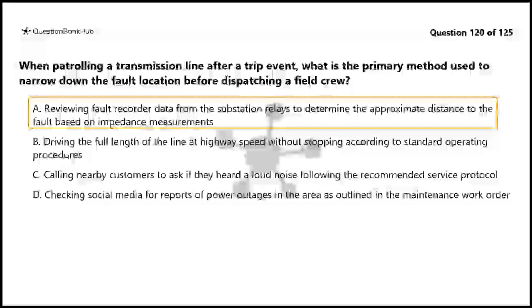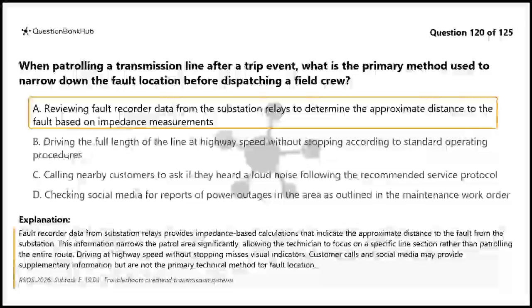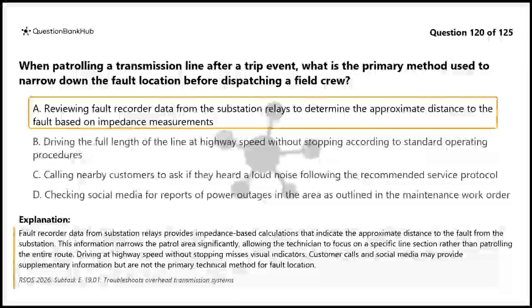The correct answer is A. Fault recorder data from substation relays provides impedance-based calculations that indicate the approximate distance to the fault from the substation. This information narrows the patrol area significantly, allowing the technician to focus on a specific line section rather than patrolling the entire route. Driving at highway speed without stopping misses visual indicators. Customer calls and social media may provide supplementary information but are not the primary technical method for fault location.